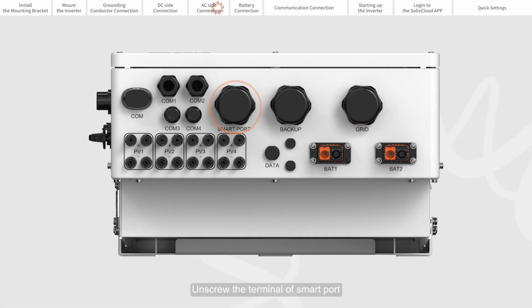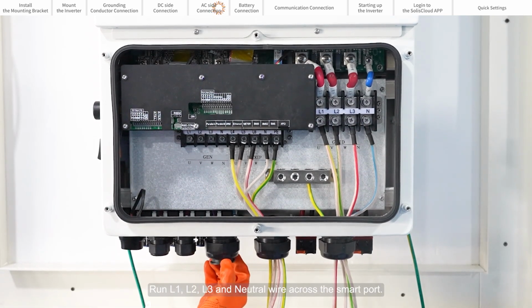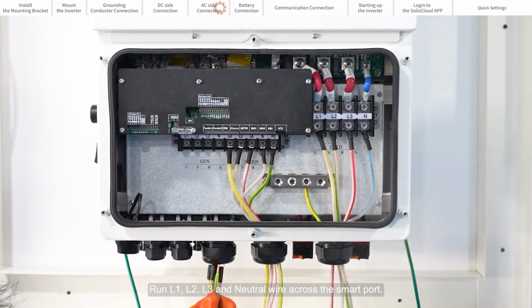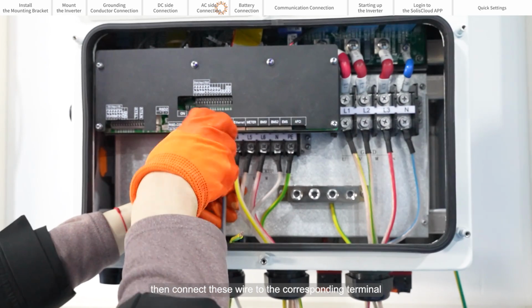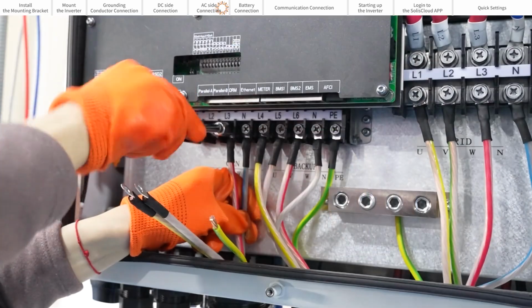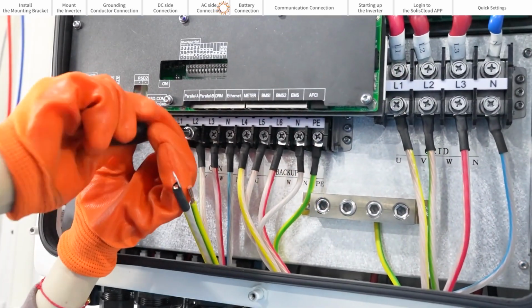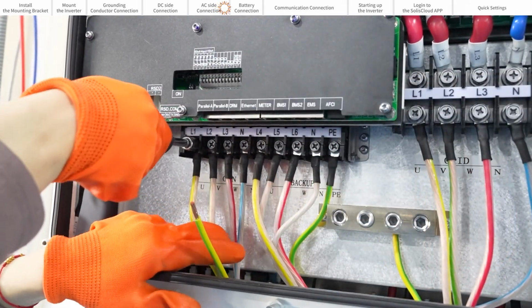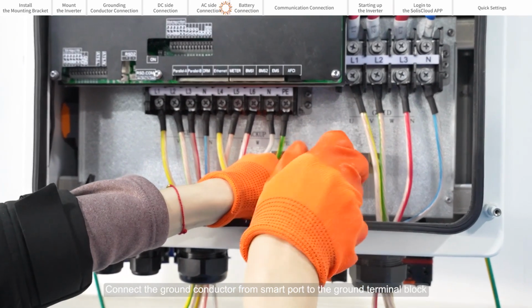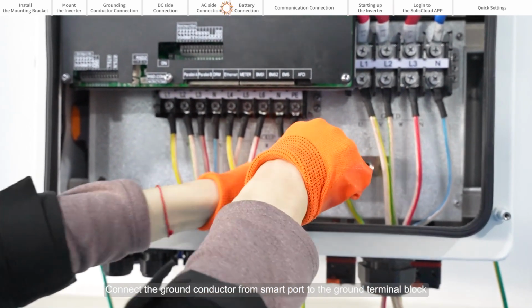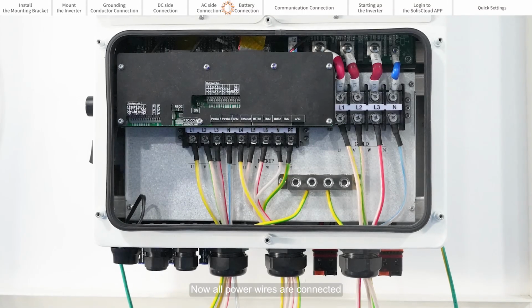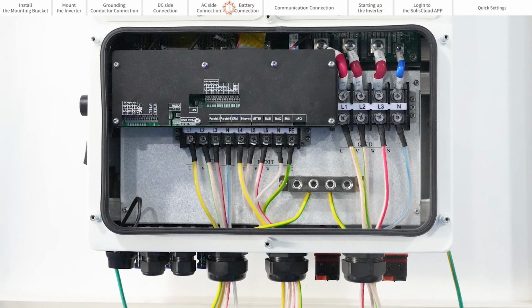Unscrew the terminal of smart port. Run L1, L2, L3 and neutral wire across the smart port. Then connect these wires to the corresponding terminal. Connect the ground conductor from smart port to the ground terminal block. Now all power wires are connected.